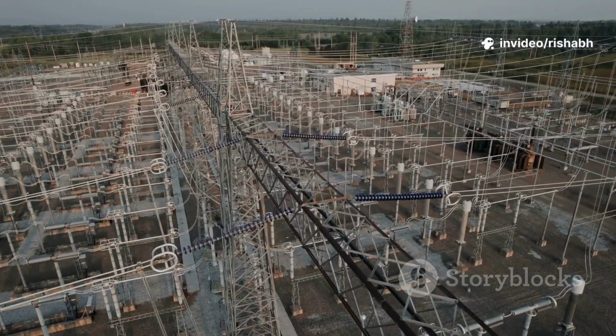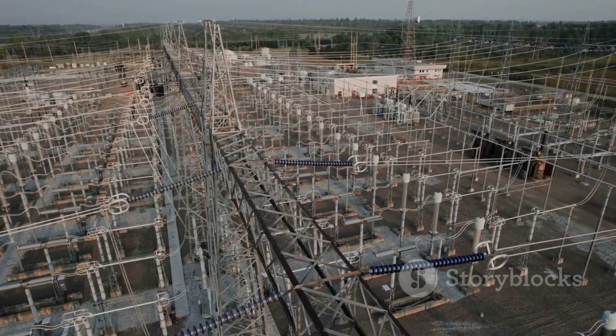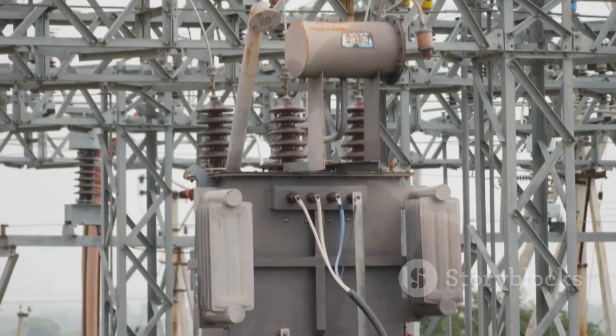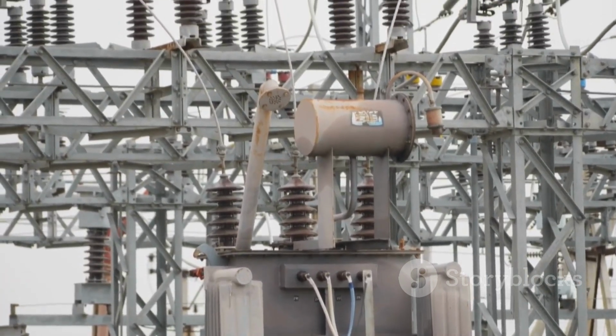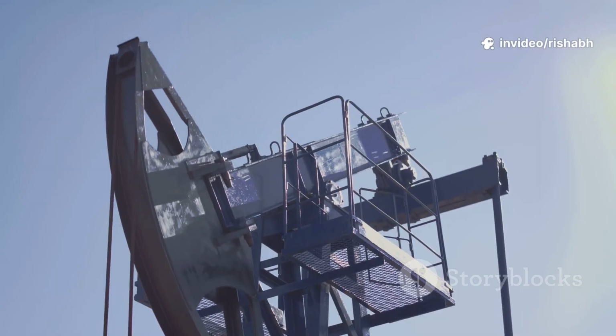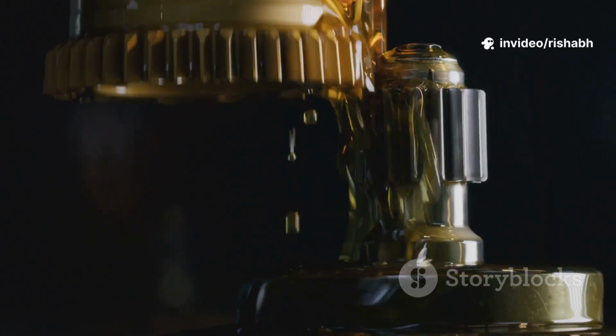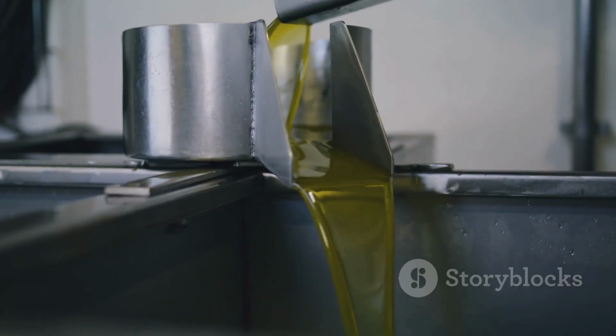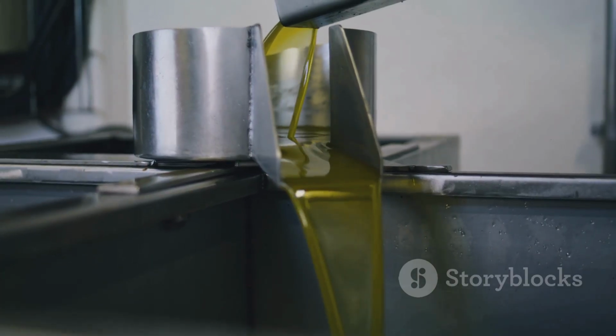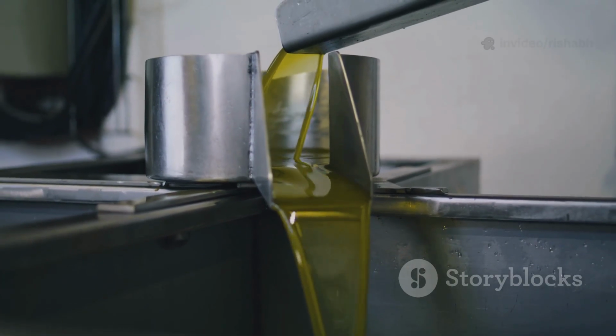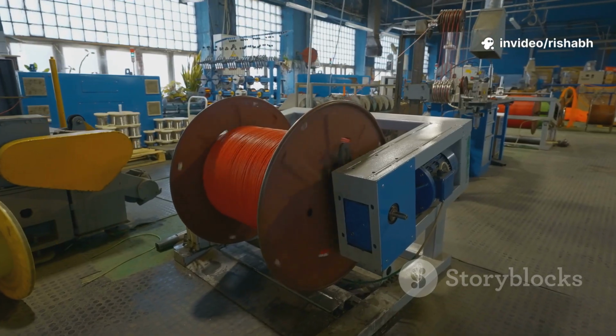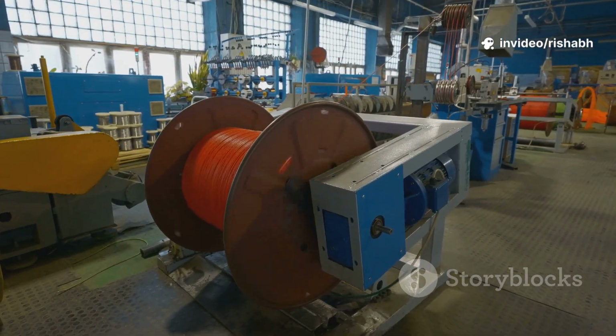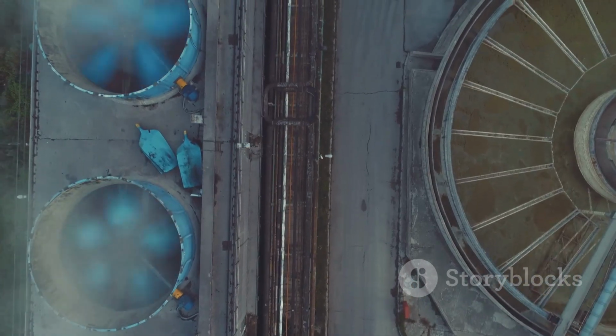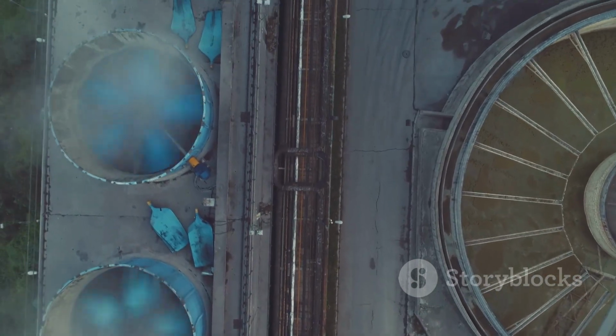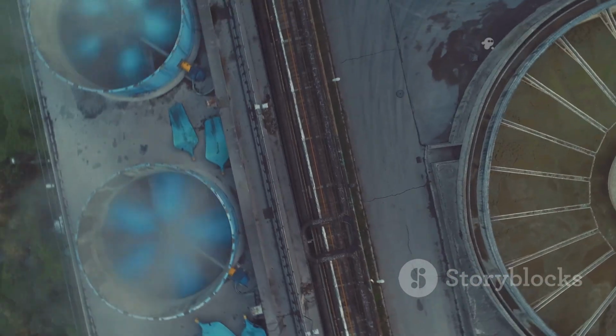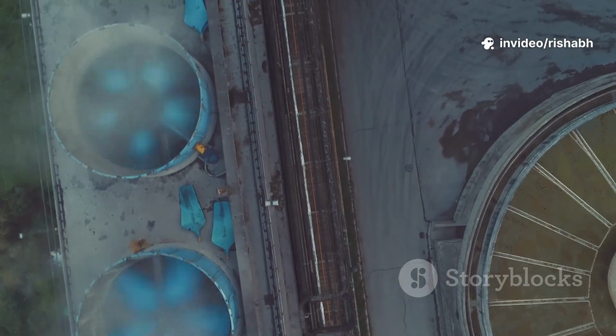For the largest and most powerful transformers, we need an even more aggressive cooling strategy. This is OFAF, or oil-forced, air-forced. In this system, we don't just rely on natural oil convection. We add oil pumps to the cooling circuit. These pumps actively force the oil to circulate from the tank through the radiators and back into the tank at a high flow rate. This forced oil circulation is far more effective at extracting heat from the windings. Combined with the forced air from the fans blowing on the radiators, the OFAF system provides the maximum cooling capacity, allowing the transformer to operate at its highest MVA rating.